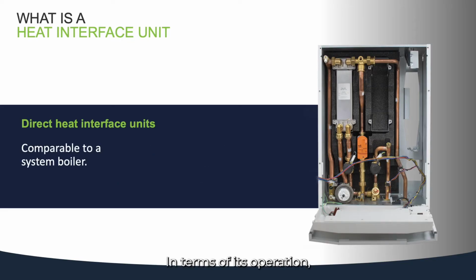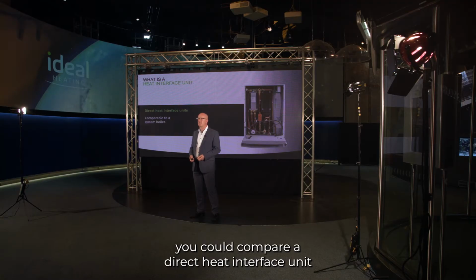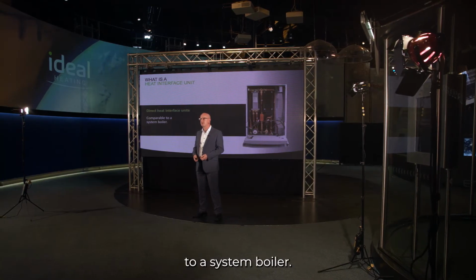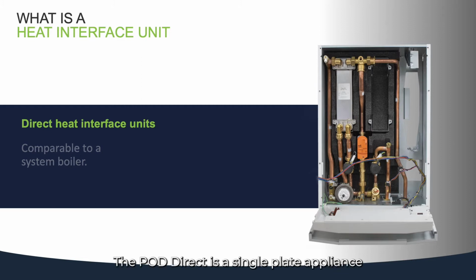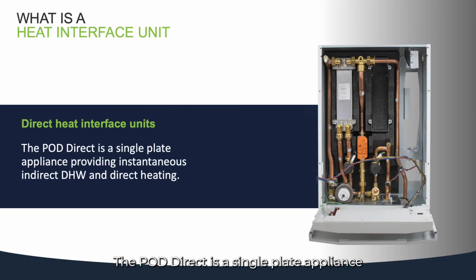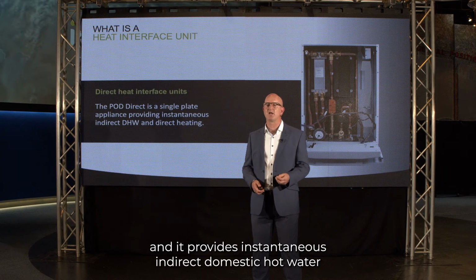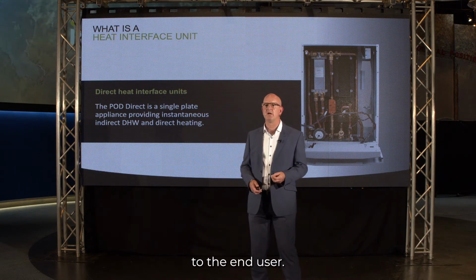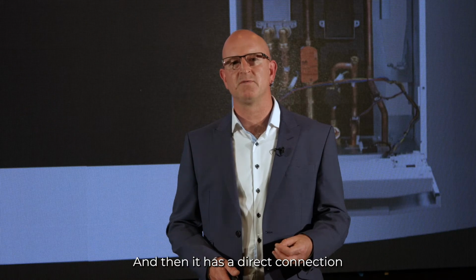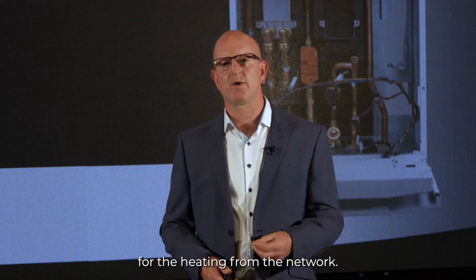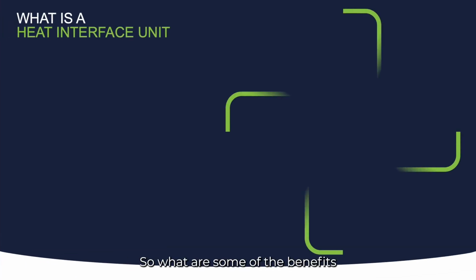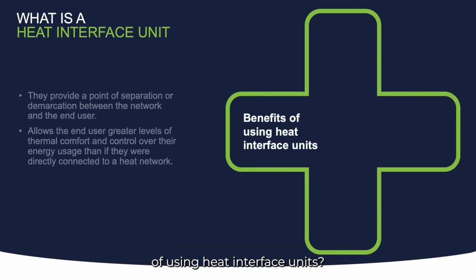In terms of its operation, you could compare a direct heat interface unit to a system boiler. The Pod Direct is a single plate appliance and it provides instantaneous indirect domestic hot water to the end user, and then it has a direct connection for the heating from the network. So what are some of the benefits of using heat interface units?